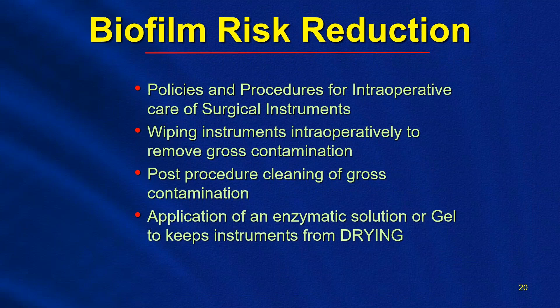So what can we do in the operating room to reduce the risk of biofilm development? Okay, we said that biofilm can form as the result of bioburden not being removed quickly and efficiently and allowed to start drying. This is why we now have policies and procedures in place for the intraoperative care of surgical instruments: wiping instruments intraoperatively to remove the gross contamination, post-procedure cleaning of gross contamination, wiping and flushing, and the application of enzymatic solutions or gels to keep the instruments from drying out before being received in central sterile for reprocessing. As we said earlier, in the operating room is the actual beginning of the reprocessing cycle.